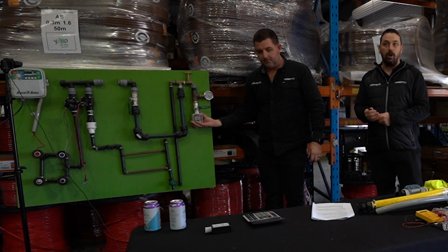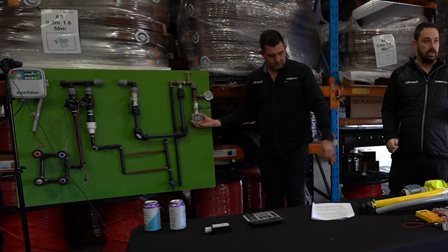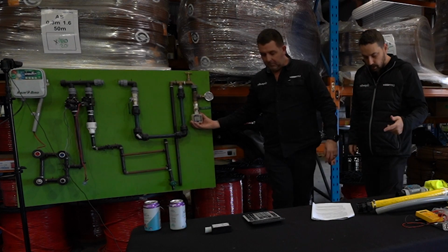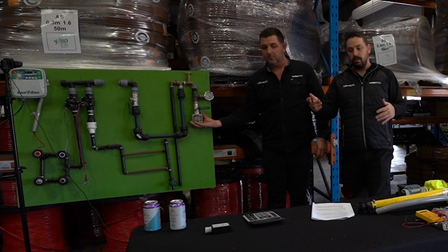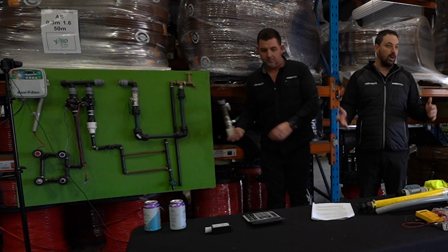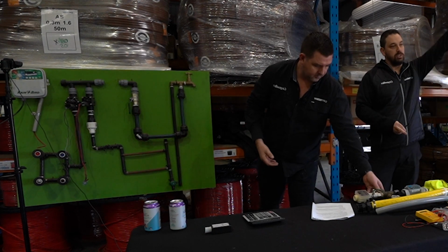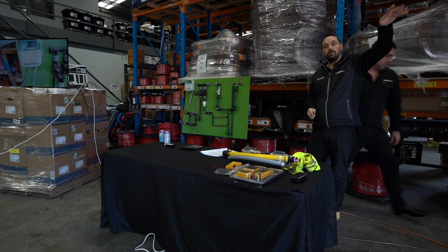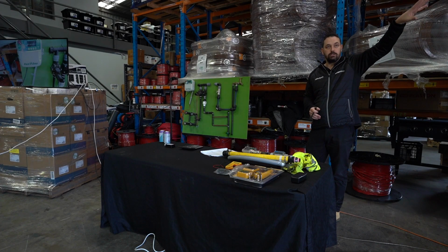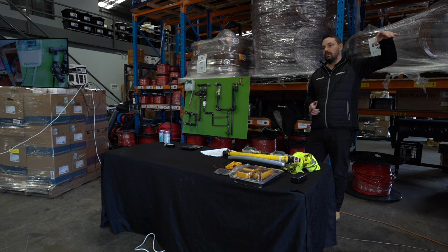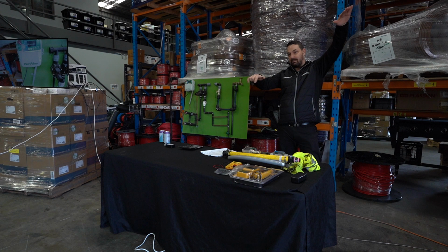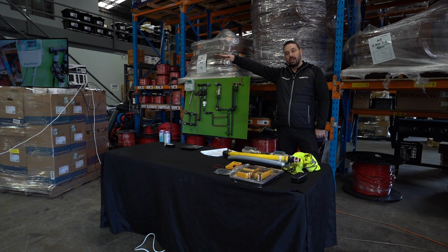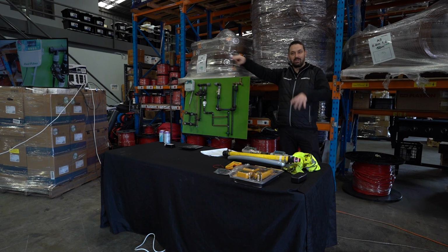Now in a township supply, in a township supply being Adelaide, we're a gravity fed system, you're going to see anywhere sort of from 250 to 550 kPa. Once you sort of get into closer up into the hills, like sort of to where I live in the northeast, you're getting sort of 8 to 900 kPa. The further you go out, obviously being gravity, we're getting closer to sea level at that point. And there's all this infrastructure as well from all these houses that come off the networks.